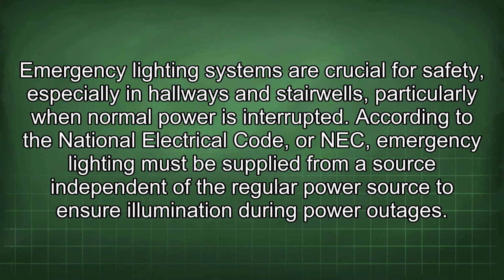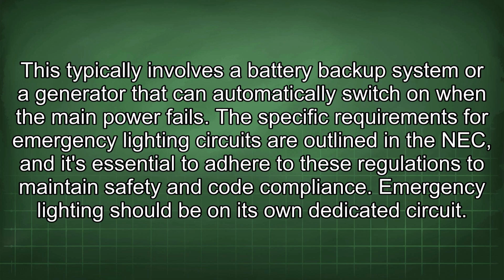Emergency lighting systems are crucial for safety, especially in hallways and stairwells, particularly when normal power is interrupted. According to the National Electrical Code, or NEC, emergency lighting must be supplied from a source independent of the regular power source to ensure illumination during power outages. This typically involves a battery backup system or a generator that can automatically switch on when the main power fails. The specific requirements for emergency lighting circuits are outlined in the NEC, and it's essential to adhere to these regulations to maintain safety and code compliance.